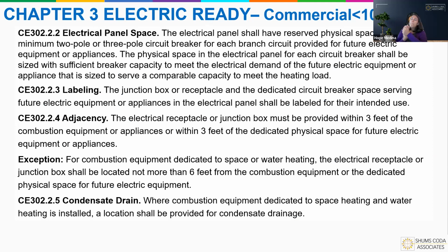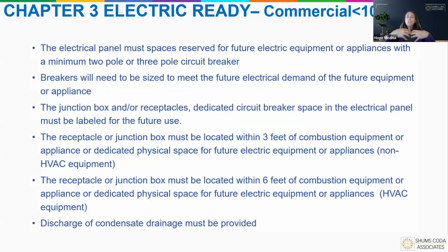Now, we talked a little bit about the idea of leading to the panel, and there is some very specific information. I know this is a lot of verbiage on the screen, so we're going to go to the more digestible information, I hope. Basically, you're going to be required to have a space, or spaces, reserved in the panel for future electric equipment or appliances. And that space has to have a minimum of a 2 or 3 pole circuit breaker associated with it. The breakers need to be sized to meet the future electrical demand of the equipment or appliance.